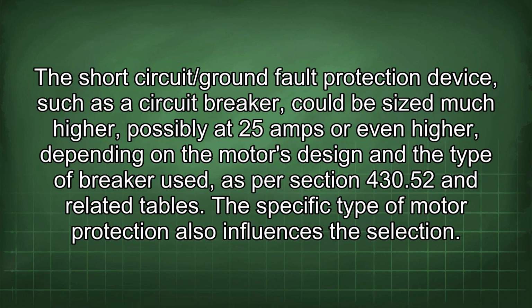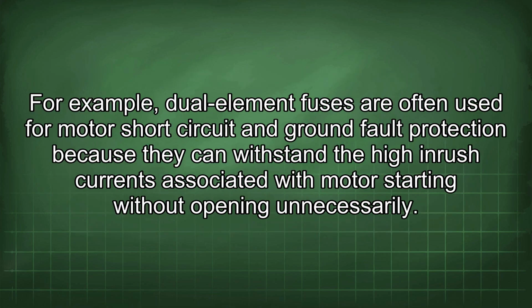The short circuit/ground fault protection device, such as a circuit breaker, could be sized much higher, possibly at 25 amps or even higher, depending on the motor's design and the type of breaker used, as per Section 430.52 and related tables. The specific type of motor protection also influences the selection. For example, dual element fuses are often used for motor short circuit and ground fault protection because they can withstand the high inrush currents associated with motor starting without opening unnecessarily.